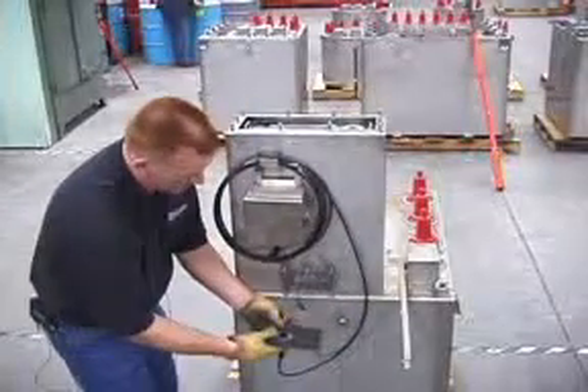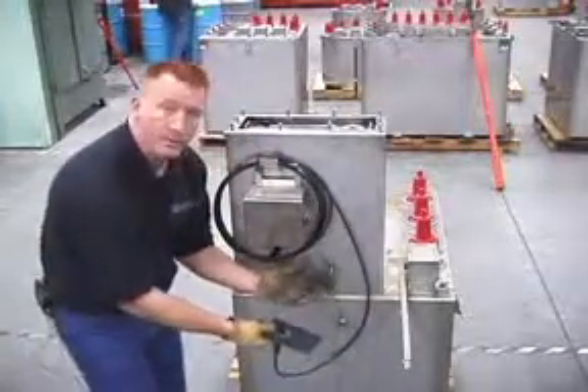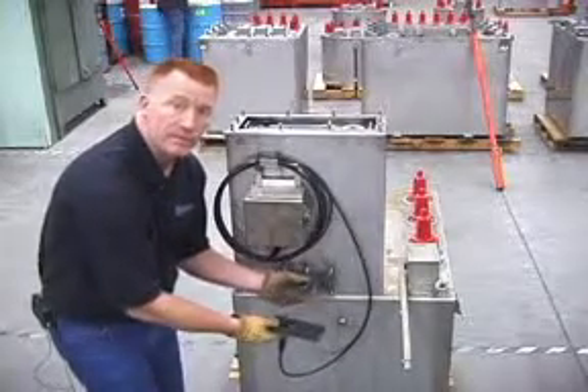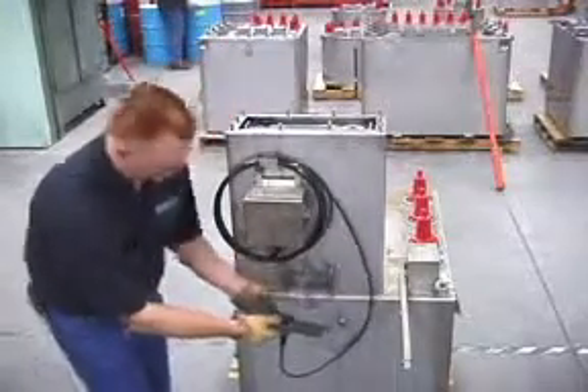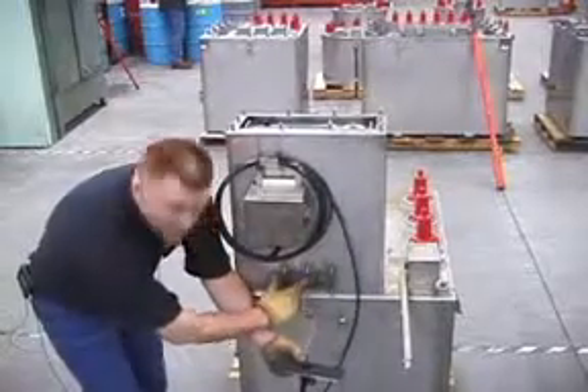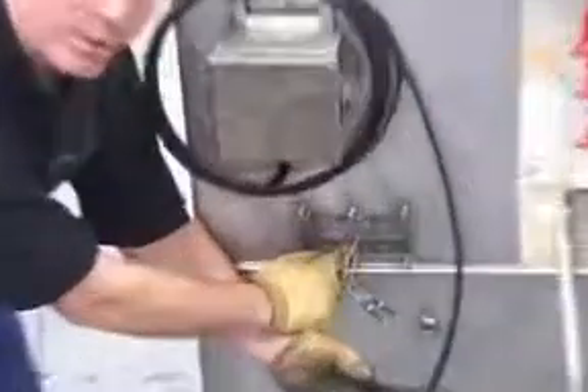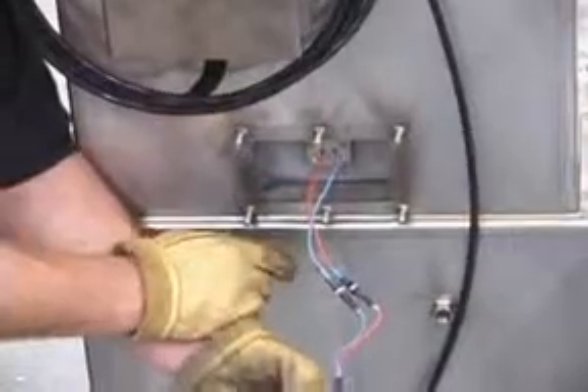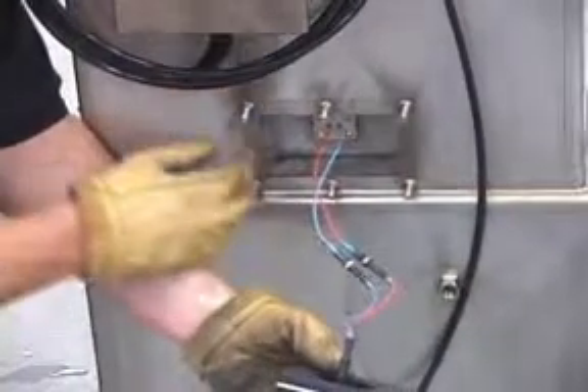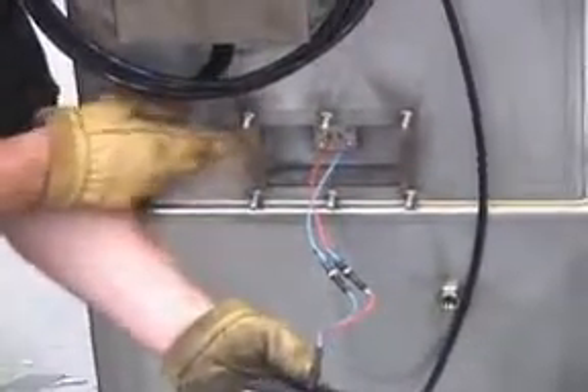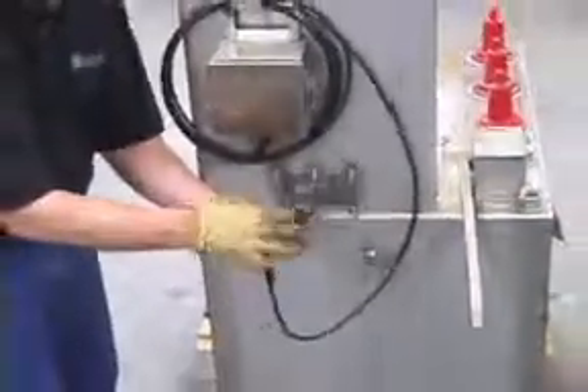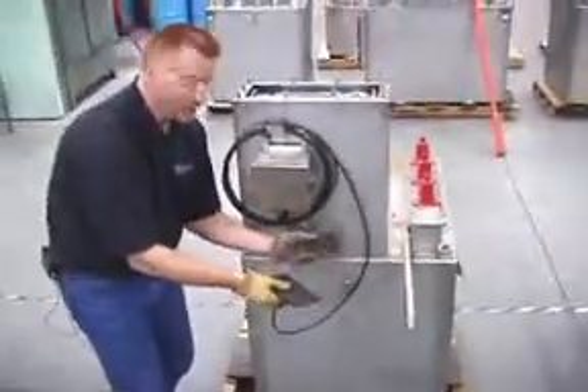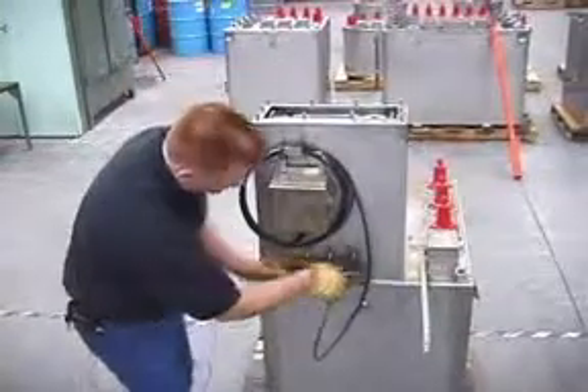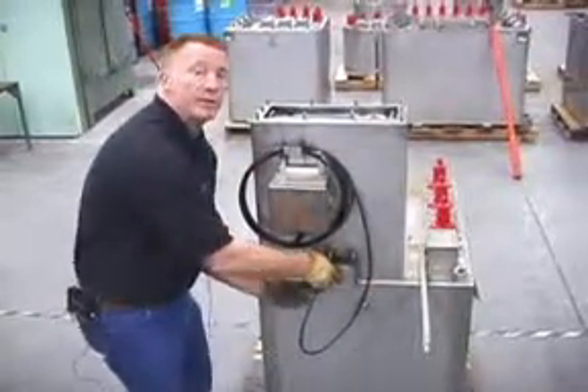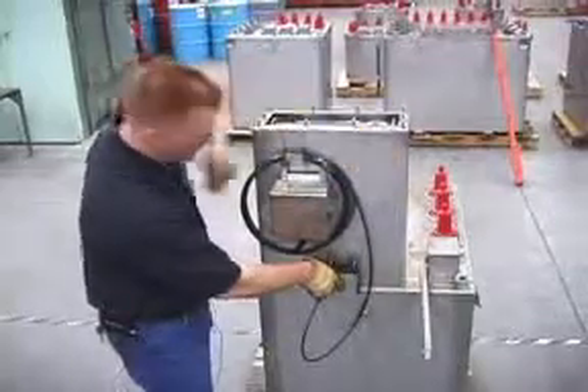Here you can see that the fiber optic cord can be easily replaced in the field should it become damaged. And the fiber optic lines coming from the control cabinet pass through a watertight bulkhead fitting from the submersible control cabinet out into the gasketed connection area, so that there's no chance of any water intrusion into the control cabinet or the high voltage compartment.